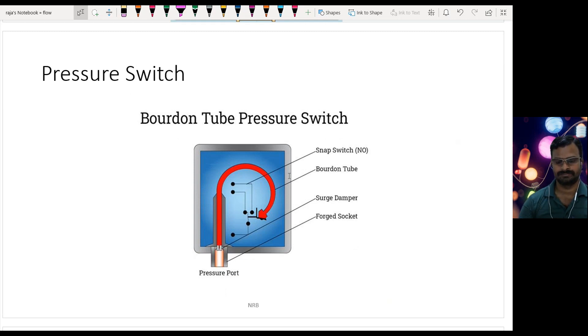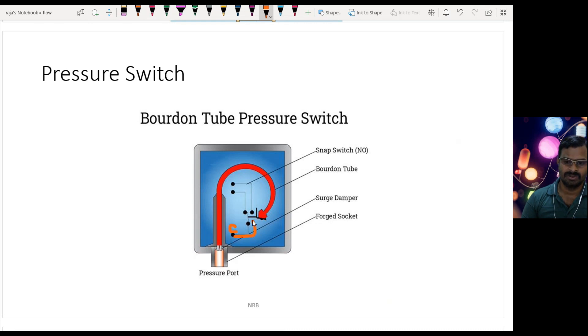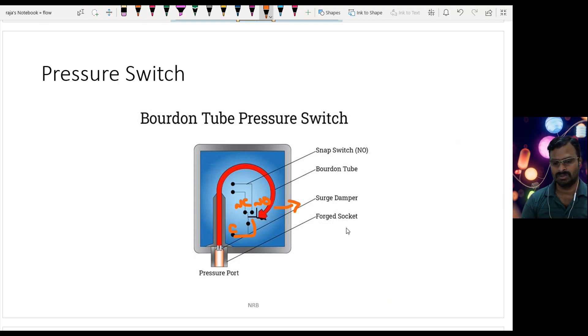The Bourdon tube pressure switch: the mechanical construction differs but the function is the same. Liquid flow goes through this Bourdon pipe, and when the pressure increases, the Bourdon pipe expands. When it expands, the contact moves from NC to NO. The input goes to the common terminal, and when pressure increases the Bourdon tube pulls the contact from NC to NO, making the circuit close from common to NO so current can flow. This signal is connected to the PLC.